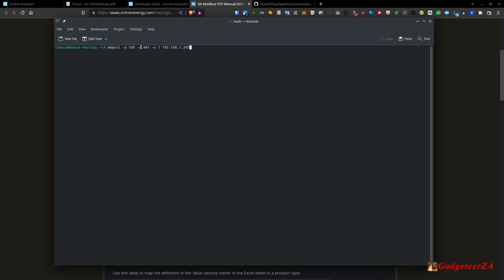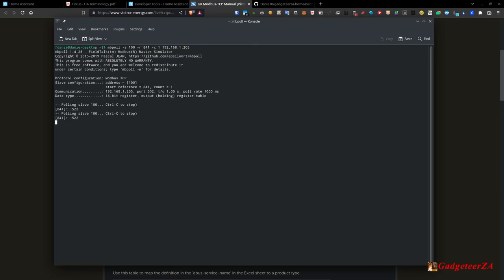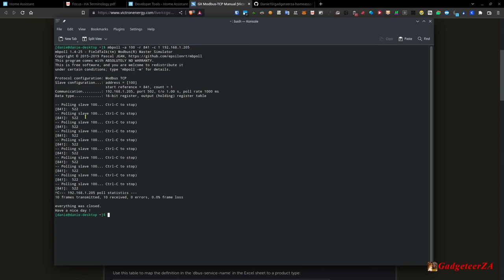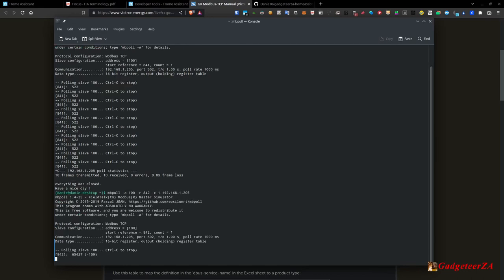One quirk: the actual register address is 840 not 841 — mbpoll seems to do a minus one, like counting from zero. Execute the command and it reads register 840 from device 100, returning 522 — which at scale 0.1 becomes 52.2 volts, with precision 0 dropping the decimal. That's why I had to adjust the scale factor. You can experiment and test until you find the right register you're looking for.